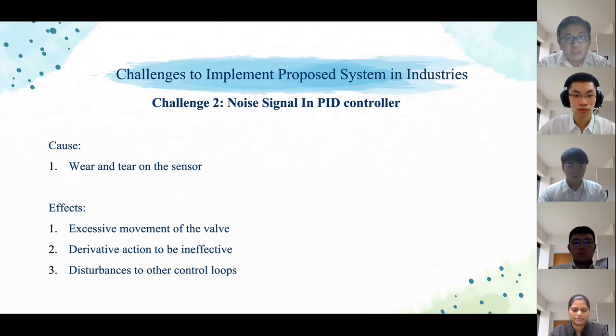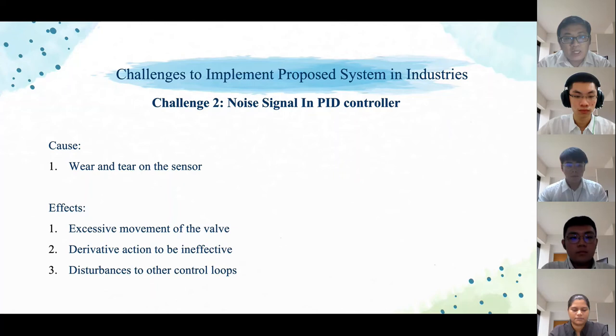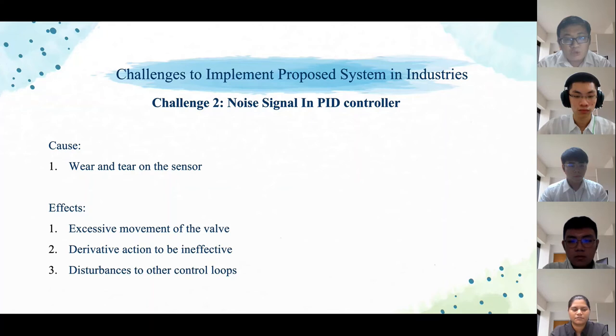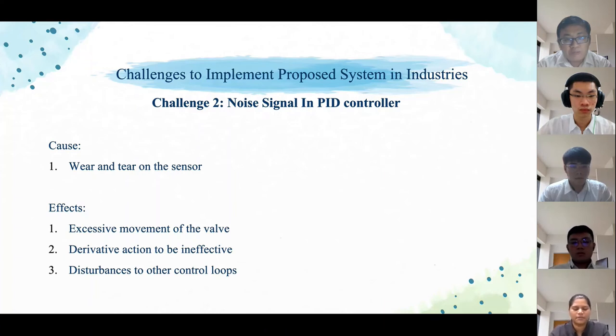The second challenge of implementing PID control is the presence of noise. Noise is a random and unwanted signal. In our control system, noise is associated with the differential pressure (DP) across an orifice plate used to infer flow rate. Noise can be caused by wear and tear on the sensor or physical operations that cause the sensor to send erratic readings to the controller. With noise present, the derivative action causes the noise in the process variable (PV) measurement to be amplified in the controller output signal, producing chattering in the valve, leading to excessive valve movement and eventual damage and wear. Additionally, noise will cause the derivative action to be ineffective due to erratic motion of the PID controller output, and the erratic output will become a disturbance to other controllers.